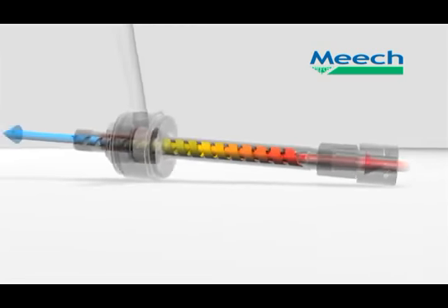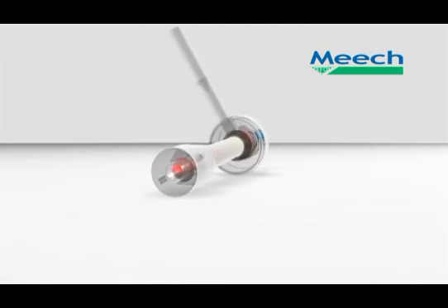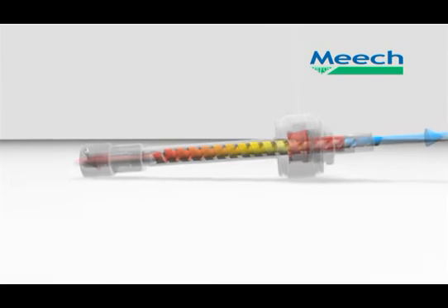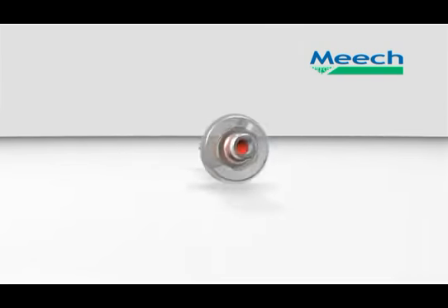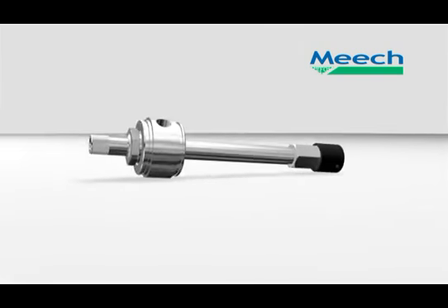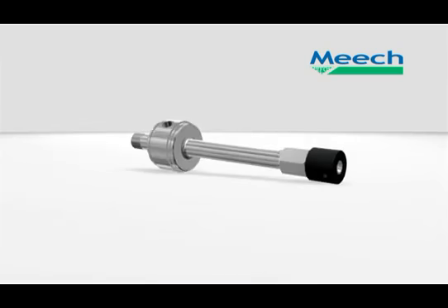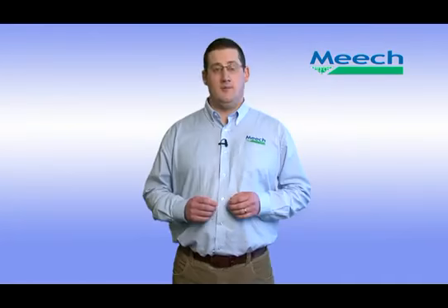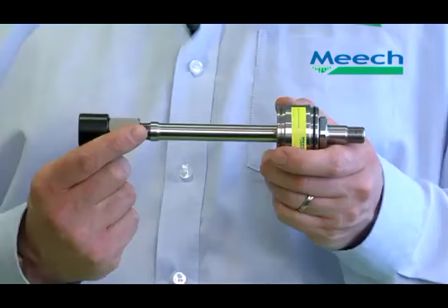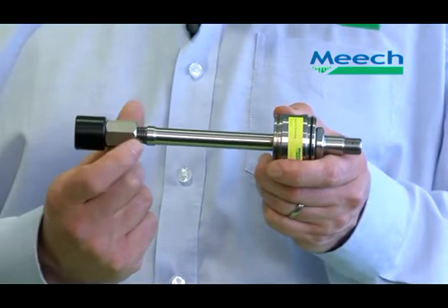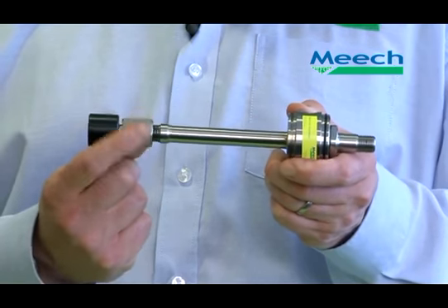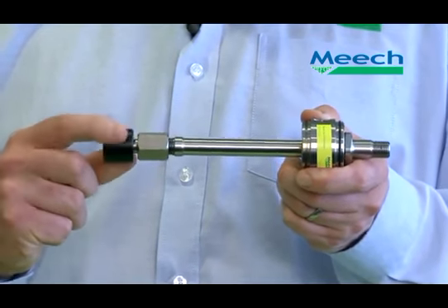The hot outer air is bled off at one end of the tube and the cold inner air at the other. The percentage of the air exiting the cold end is called the cold fraction and is adjustable by a control valve. The cold fraction can be controlled and adjusted in two ways. Firstly, you can adjust the control relief valve. This controls the balance between airflow and temperature.